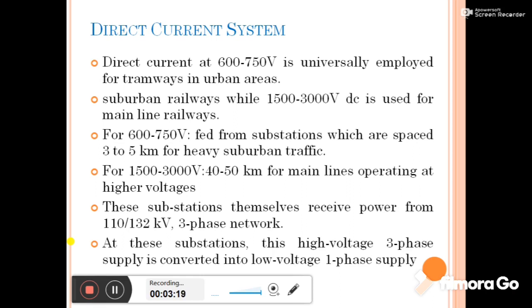When the voltage level increases, the current decreases. If the current decreases, the voltage drop decreases, so we are able to maintain the same voltage from sending end to receiving end. That's why substations are spaced 40 to 50 kilometers apart at higher voltages.